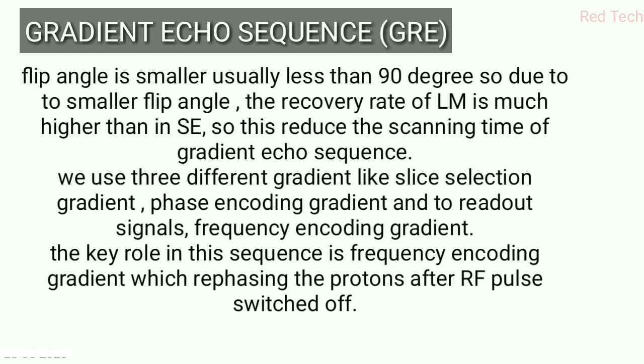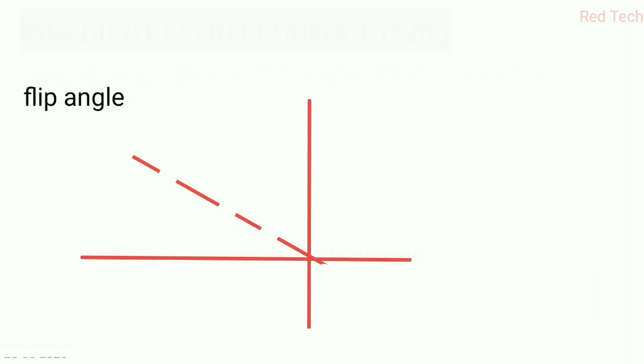Using a smaller flip angle increases the recovery rate of longitudinal magnetization, which reduces the scan time compared to Spin Echo — this is the main advantage of the GRE sequence. We use three gradients: slice selection, phase encoding, and frequency encoding. As you can see in the diagram, the smaller flip angle allows hydrogen protons to recover their state very quickly. That covers the Gradient Echo sequence.